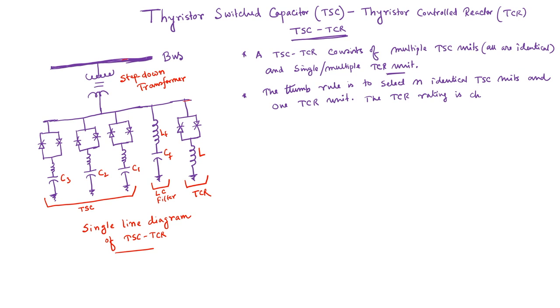such that its rating is 1/n of the total rating of TSC. This is a thumb rule, not necessarily that you have to follow this rule, but this is a thumb rule in designing TSC-TCR.